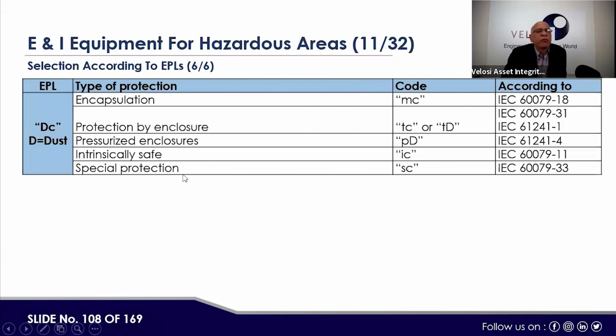If a junction box is there, what kind of isolation do we need to implement there? If there is a motor, we know that in a motor there's inside wiring, so what kind of protection, what kind of enclosure is required so that it does not cause a spark for the hydrocarbon around the pump or around the motor in that area? So the first selection is called EPL, to protect in that particular hazardous area classification.